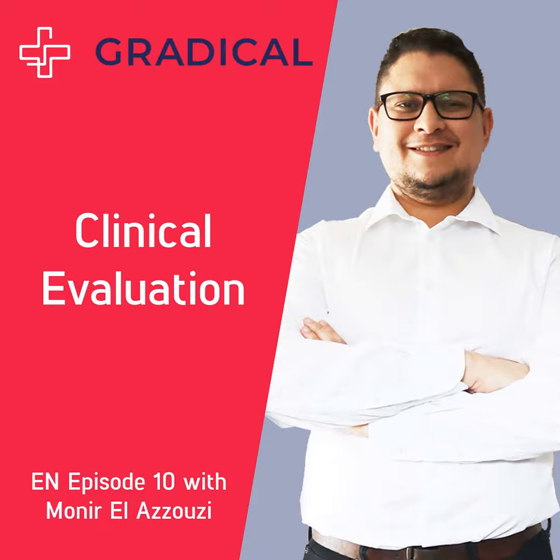On clinical evaluation, we have a concept called well-established technology, WET, W-E-T. Mainly, a well-established technology is a technology that has been on the market for many, many years, and we have enough data to prove that everything is fine. There is a standard for it. Everything is there. As long as you follow the recipe of the device, it's working.